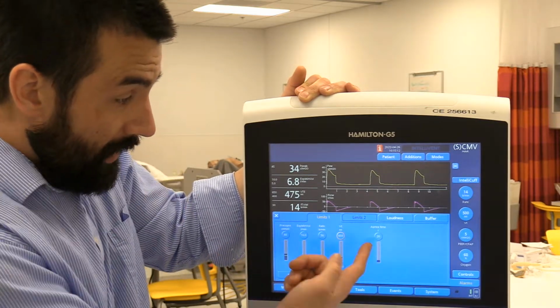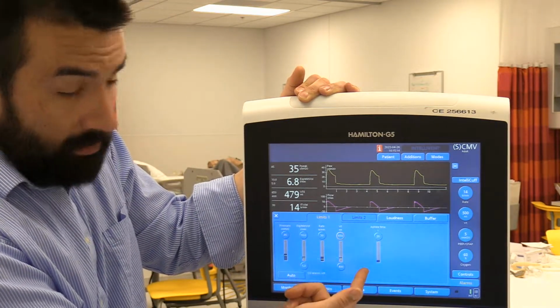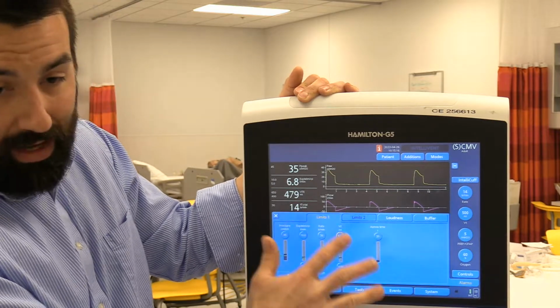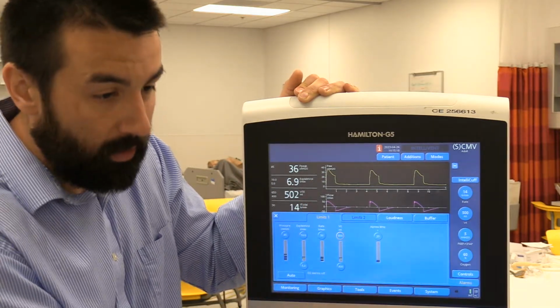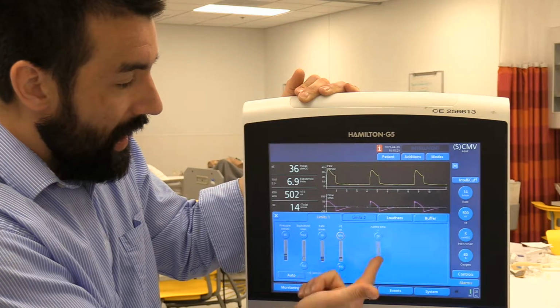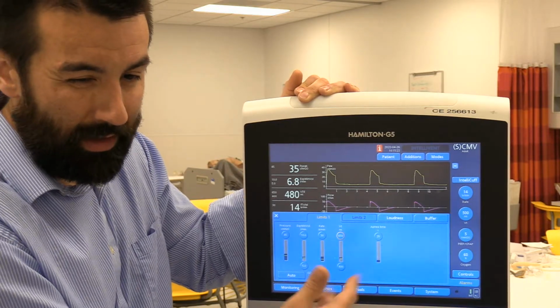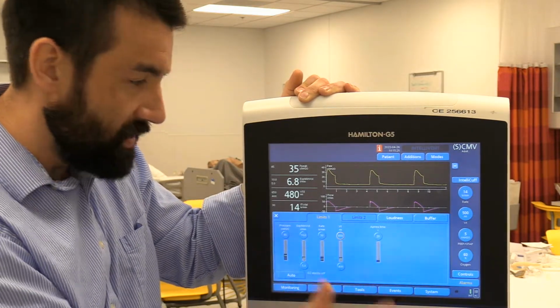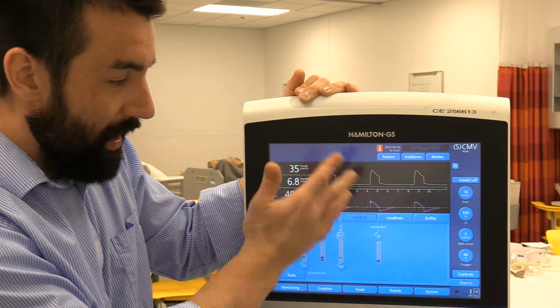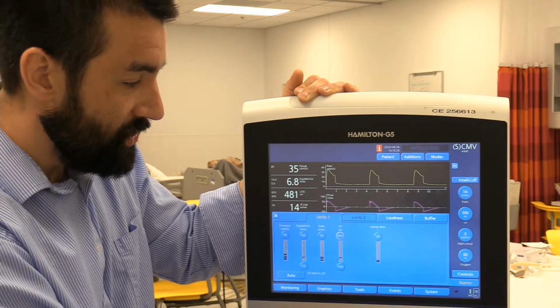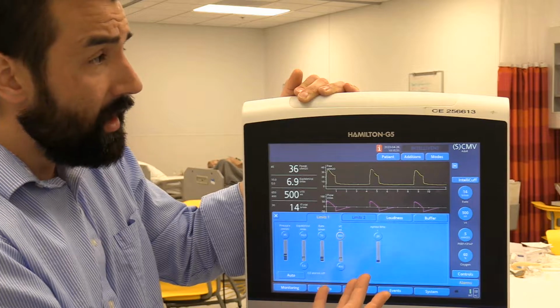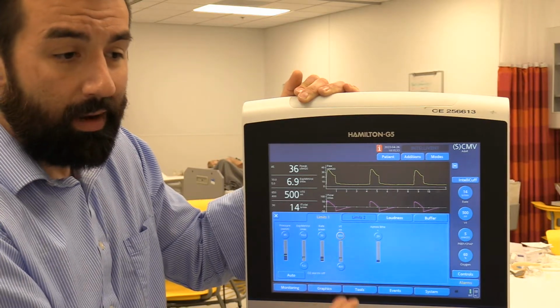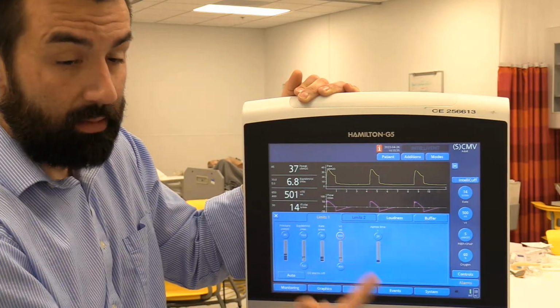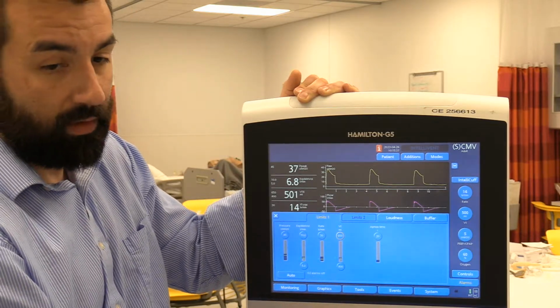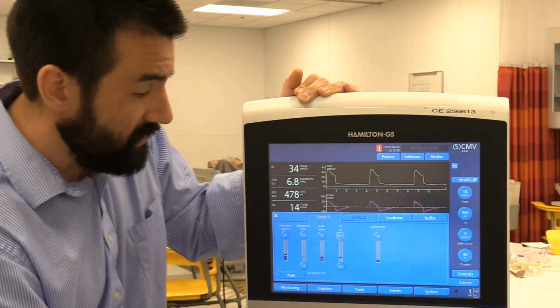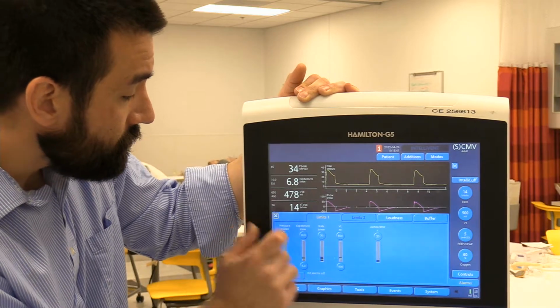Things we'll get into. Apnea time. You set an apnea time, but on the Hamiltons, in a mode like this where you can't truly go apneic and not get any support, you're not going to have any apnea settings. If you run an IMV or something with a really, really low rate, yes, you can have backup settings taking place, but it should not be an issue here. 20 seconds is pretty standard. If you are running a mode where a patient could go apneic and you want appropriate backup settings, you want to go ahead and confirm those. And this vent defaults to doing those as pressure ventilation.